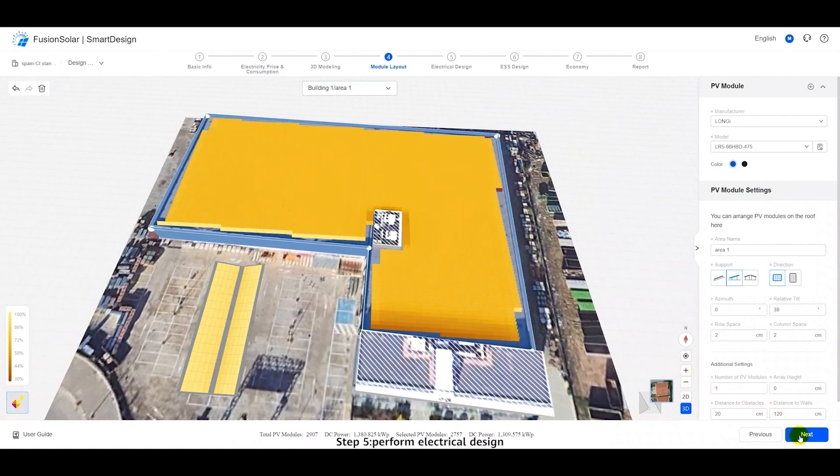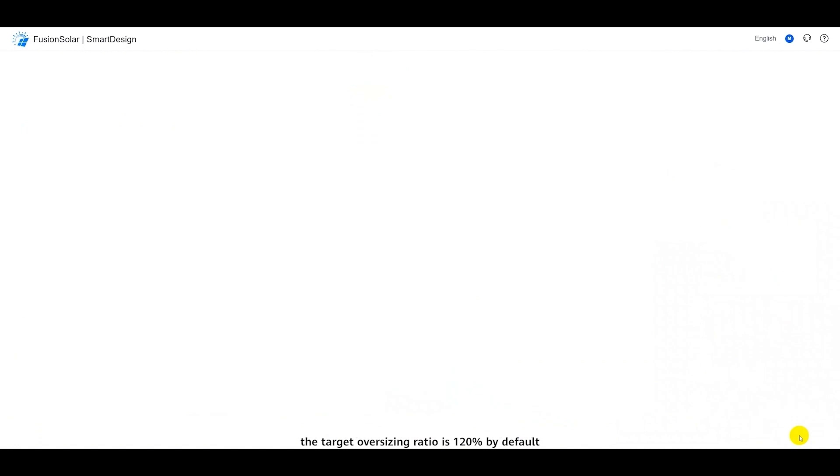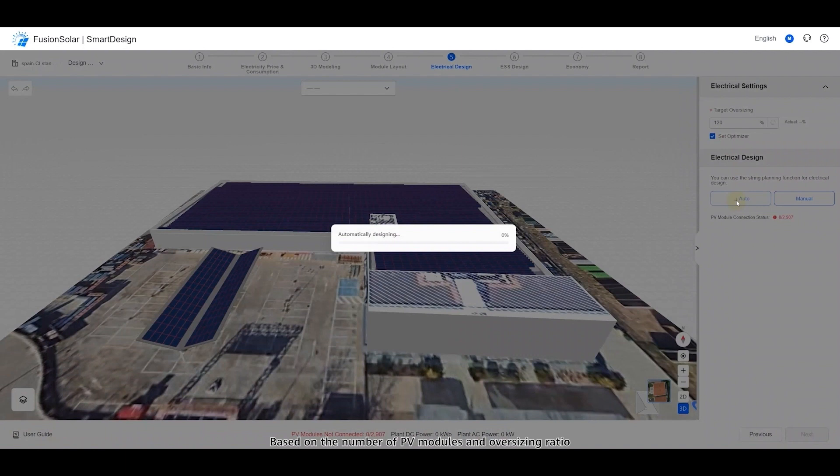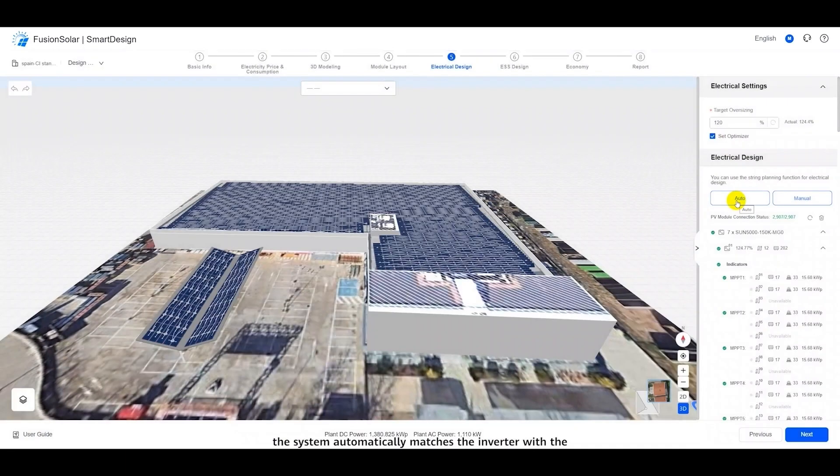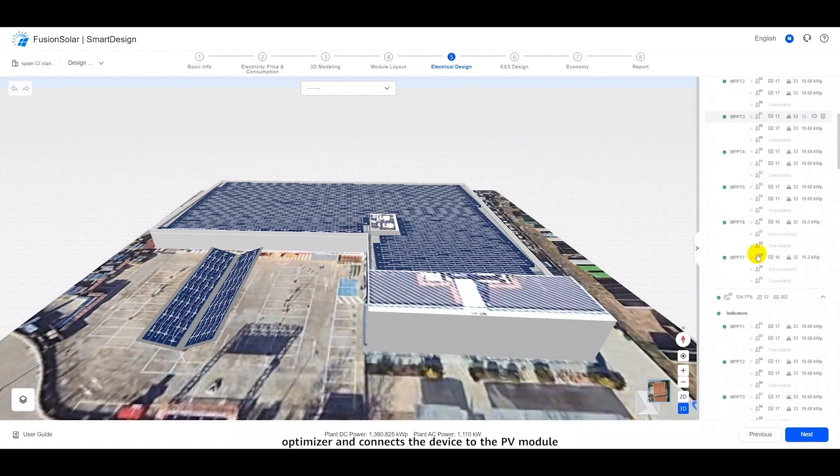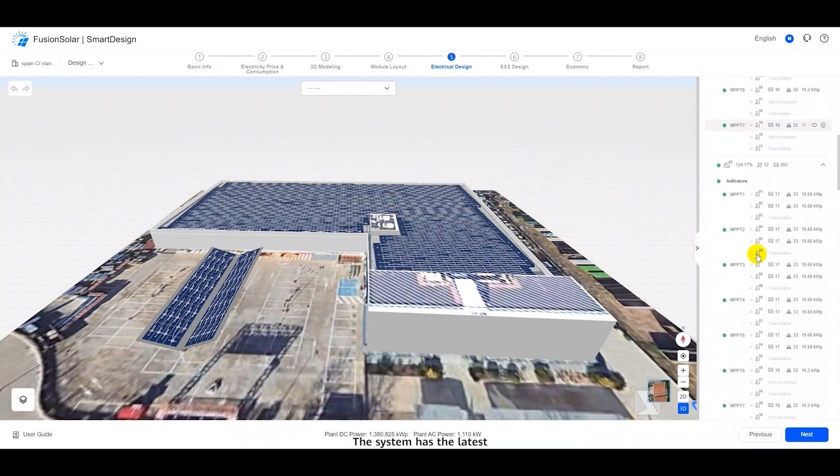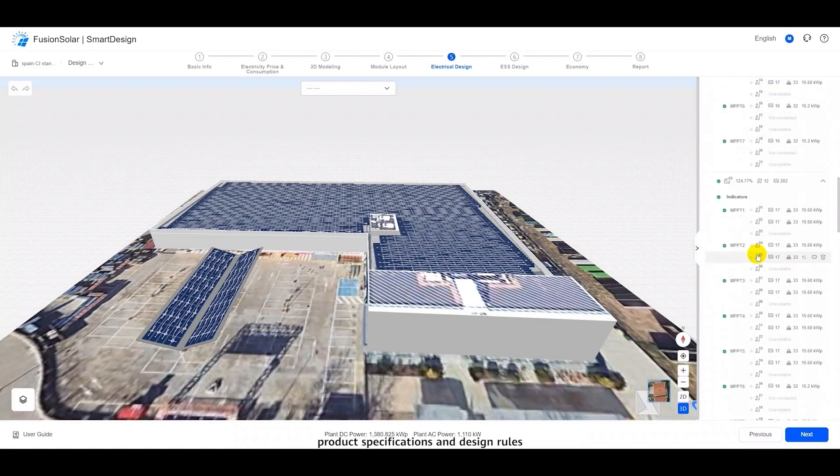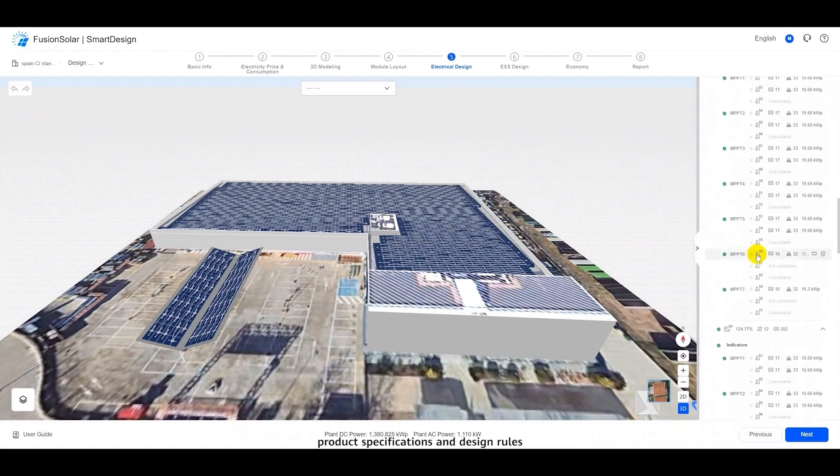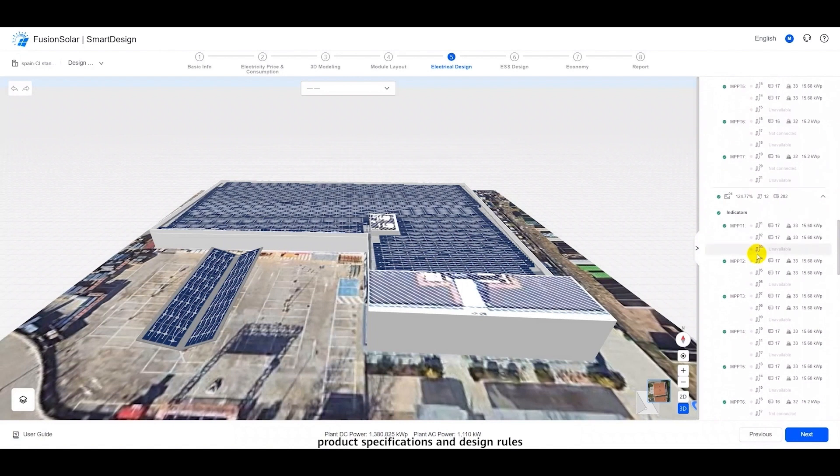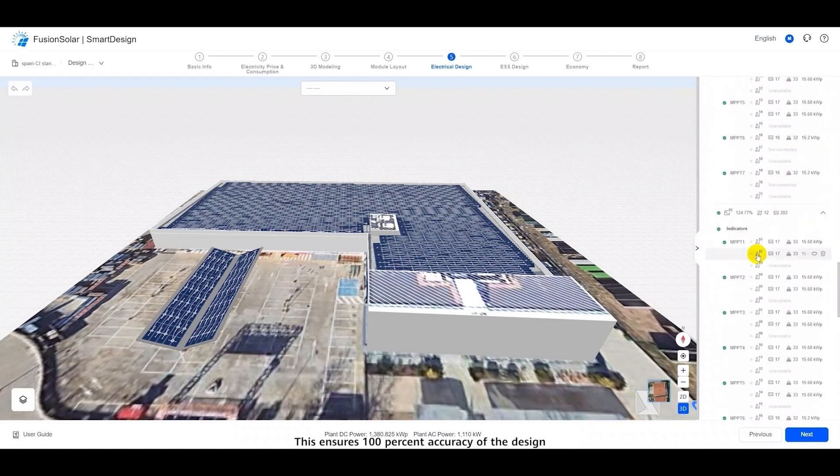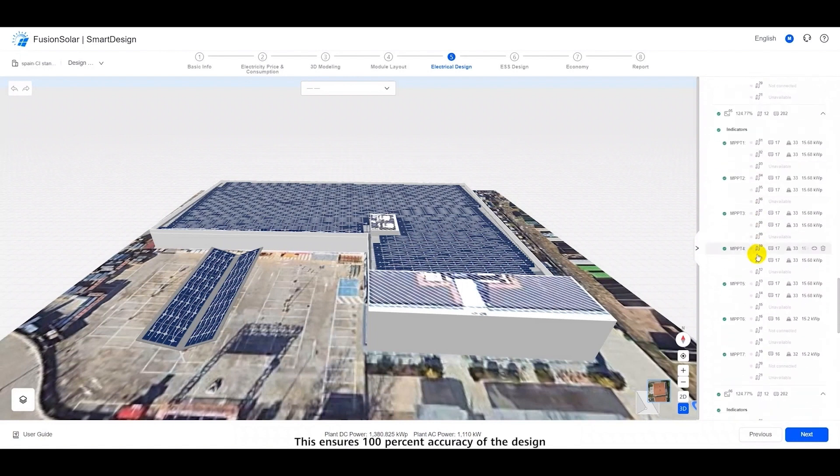Step five, perform electrical design. The target oversizing ratio is 120% by default. Select the optimizer and click Auto Design. Based on the number of PV modules and oversizing ratio, the system automatically matches the inverter with the optimizer and connects the device to the PV module. The system has the latest product specifications and design rules. This ensures 100% accuracy of the design.